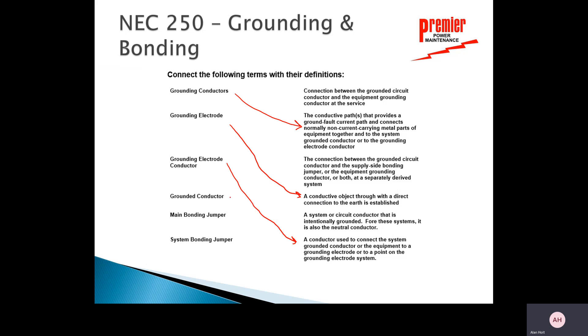The grounded conductor — this was difficult for me in my younger years — is a system or circuit conductor that is intentionally grounded. On the systems we deal with now, that's our neutral. It is not the grounding conductor, but it is a grounded conductor. Back at the source we actually connect that to the grounding system, so it's often referred to as the neutral conductor.